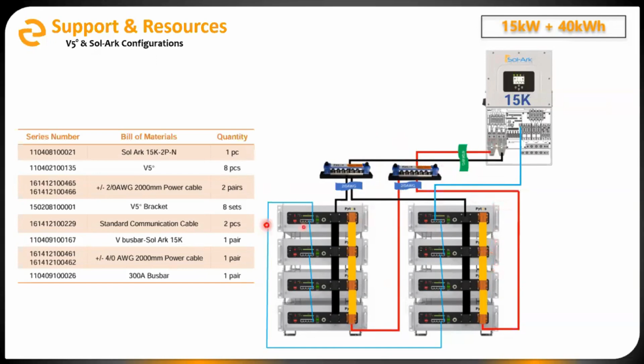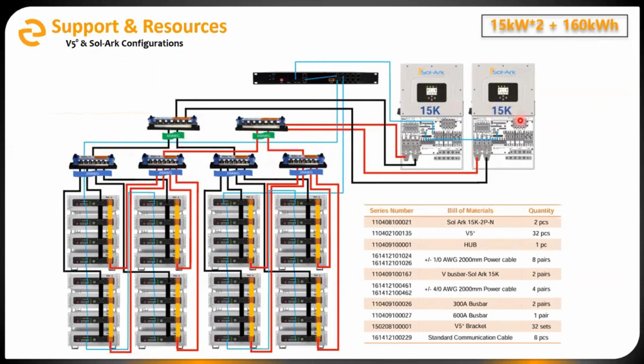This next one's a little bit bigger. It's not a fully populated system, but just a larger scaled system - 32 batteries, 160 kilowatt hours of storage. Because we have more than 16 batteries, we're using our hub accessory. This example also has 2 inverters, so a little unique. Depending on where batteries are housed, distances, and what size cable we'd like to use, we may not need all of the busing that's being shown here, but you can see what's happening: we're using lower amp rated bus bars to combine the cabinets, and then higher amp rated bus bars between that and the inverters.